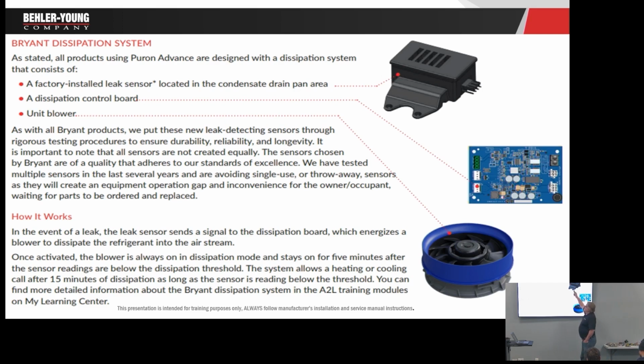So what it'll do is, if it detects that, okay, hey, I got a leak, it's going to shut the heat off, it's going to shut the air conditioning off, and it's going to turn the blower on. Okay, what's it doing? Because what it wants to do is dilute that refrigerant throughout the entire space. If we dilute it, we can never get to our 12%. Even if we did get to 12%, we still can't light it anyway, because it's really hard to light. So that's what it's doing. Okay, so we're going to talk about that first.